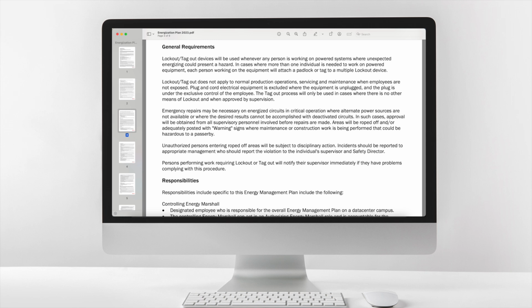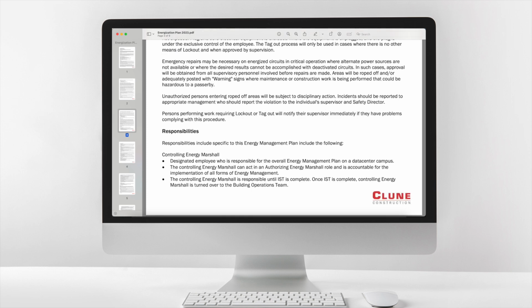Incidents should be reported to appropriate management, who should report the violation to the individual's supervisor and safety director. Persons performing work requiring lockout or tagout will notify their supervisor immediately if they have problems complying with this procedure. Responsibilities specific to this energy management plan include the following. Controlling energy marshal: designated employee who is responsible for the overall energy management plan on a data center campus. The controlling energy marshal can act in an authorizing energy marshal role and is accountable for the implementation of all forms of energy management. The controlling energy marshal is responsible until IST is complete. Once IST is complete, controlling energy marshal is turned over to the building operations team.